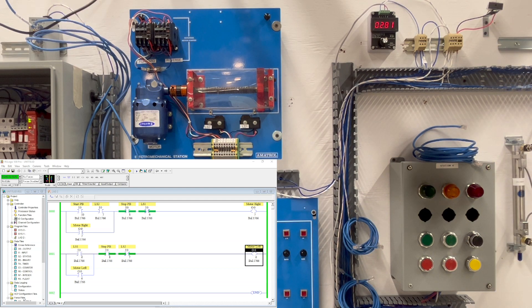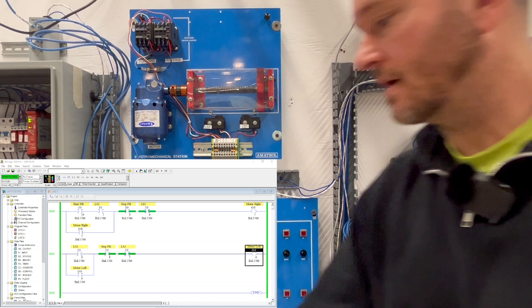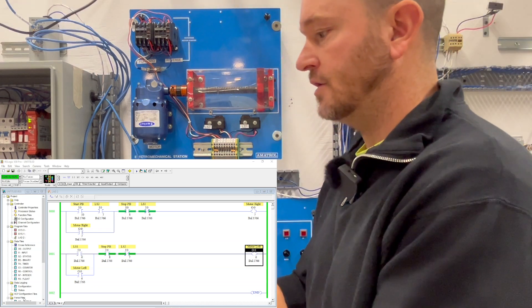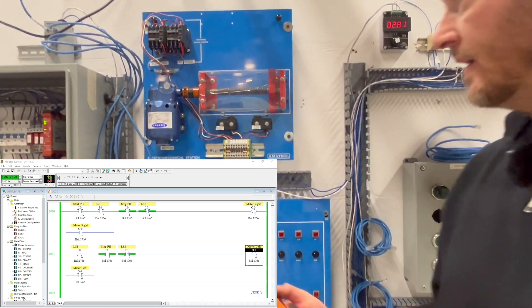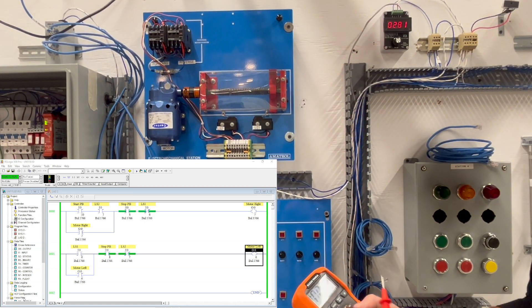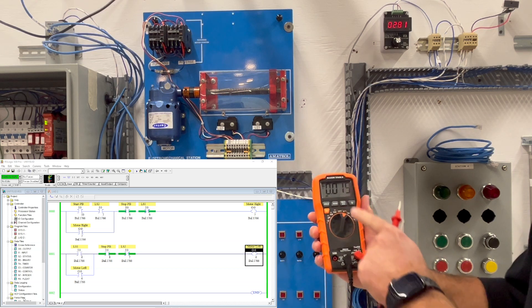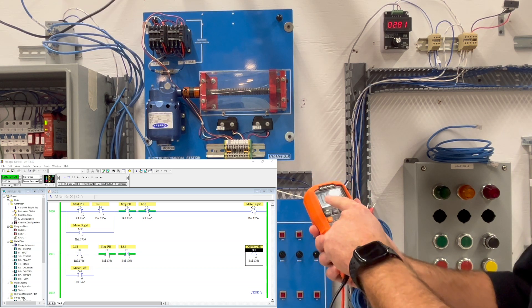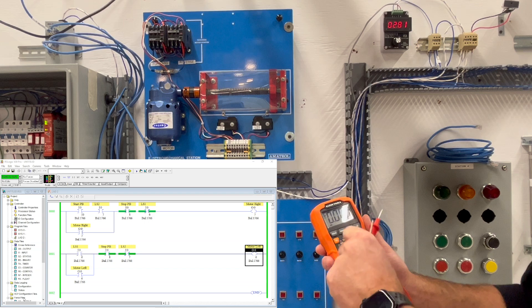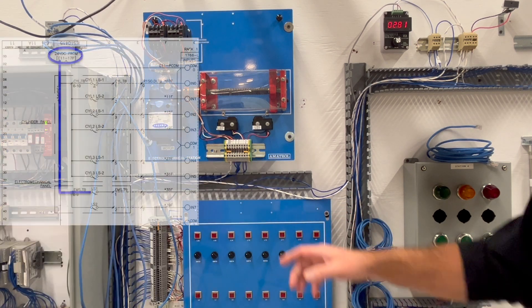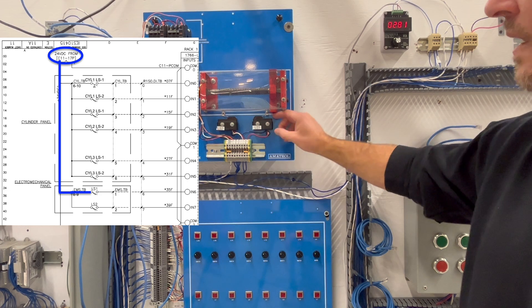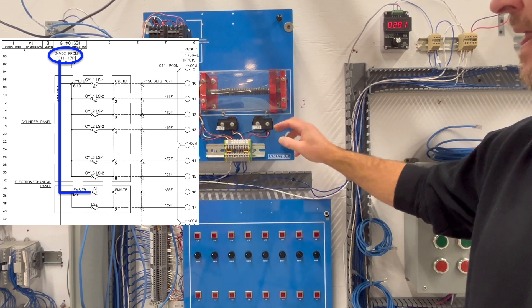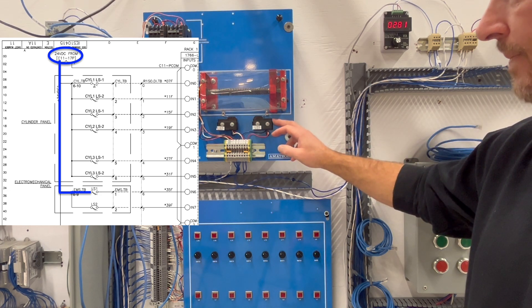To troubleshoot this, the first thing that I want to do is I like to come through and just begin to check voltages. So the first thing I do is I want to check, I turn it on to volt, my meter on the voltage. Then this is preset to AC, according to my schematic diagram for LS1 here, the problem exists. This is a DC circuit.